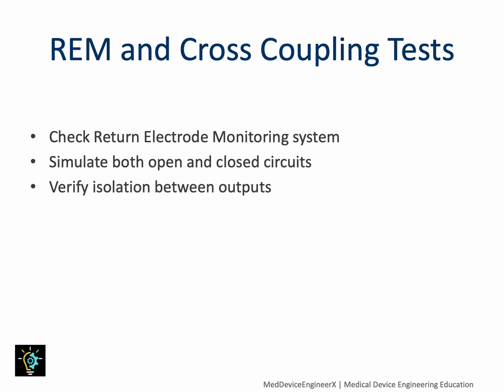The Return Electrode Monitoring System, or REM, ensures proper patient contact. Using your analyzer, simulate both normal and disconnected conditions. The FT10 should immediately detect the change, displaying a warning and blocking activation. Then, test each output channel to confirm isolation, known as cross-coupling prevention. These steps validate patient safety and confirm the generator can detect electrode faults accurately.